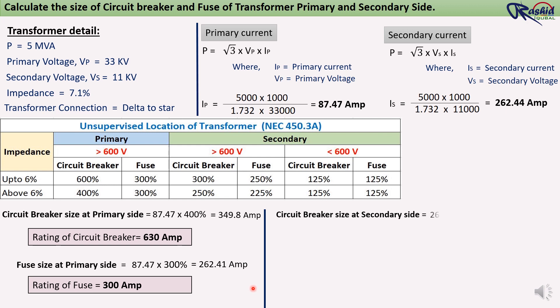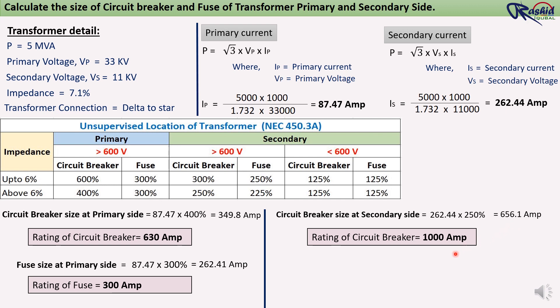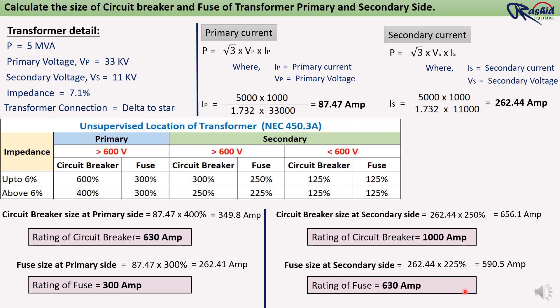Circuit breaker size at the secondary side = 262.44 × 250% = 656.1 ampere, since the secondary voltage is more than 600 V. So the breaker size will be 1000 ampere. For the fuse, multiplying 225% by the secondary current: 262.44 × 225% = 590.5 ampere. The fuse size we will use here is 630 ampere for the secondary side of the transformer.